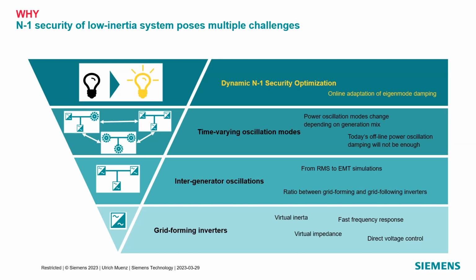You expect different generation mixes changing from hour to hour, day to day, week to week. There are times when you have inverter-only systems, times when systems are dominated by synchronous generators, and mixes in between. The larger your system and the more generation units you have, the more of these different changes you get, leading to time-varying eigenmodes of the system.